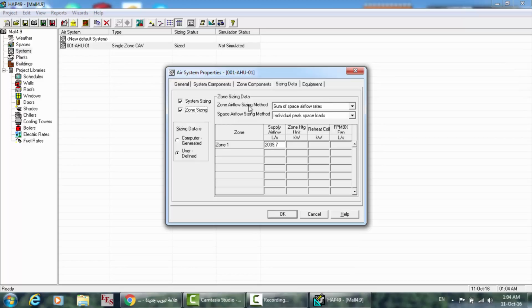For zone sizing, you have here zone airflow sizing method: sum of space airflow rates or peak zone sensible load. It will be calculated according to the peak load of this zone, and you have here 3 choices. If you choose coincident space loads, it will be calculated according to the peak of the zone, and then the flow rates will be divided. Here the coincident space loads will be distributed, the airflow will be distributed according to the peak of the zone.